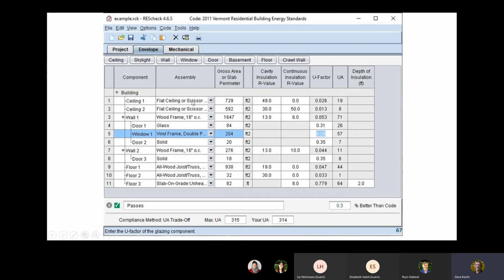So you'll choose from a drop-down there, and you'll put the area of that ceiling here, and then you will put the insulation R value in one or both of these 2 columns. You'll notice there's cavity insulation and continuous insulation, and these mean exactly what they sound like. Cavity insulation is insulation that is separated by framing. Continuous insulation is insulation that has no breaks in it. In this case, this was filled out by somebody else a long time ago, but it has R49 for cavity insulation and no continuous insulation. You can put entries in one column or both, whatever is appropriate to what you're describing.